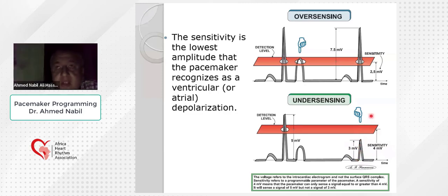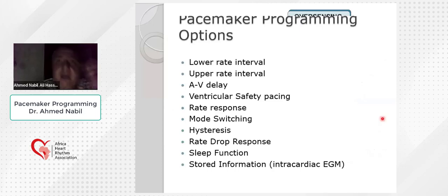So measuring the sensing and adjusting the sensitivity value according to the sensing test is very important. I should not set the sensitivity at very low values, and also I should not set it at very high values.